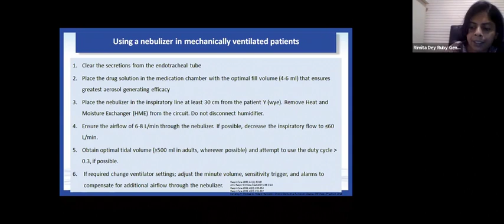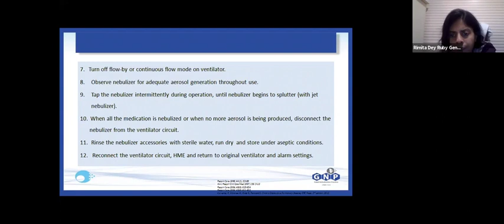You can turn off the continuous flow or flow mode on the ventilator if it actually creates a problem. Observe the nebulizer for adequate aerosol generation throughout its use, right? So you need to see the mist. If there is no mist, probably your nebulization is not working properly. You can tap the nebulizer intermittently during operation until the nebulizer begins to splutter with a jet nebulizer. When all medication is nebulized and when there is no aerosol being produced, disconnect the nebulizer from the ventilator circuit. Rinse the nebulizer accessories with sterile water, run dry and store under aseptic conditions. I don't know how frequently it is done in our ICUs. Reconnect the ventilator circuit, HME, and return to the original ventilator and alarm settings. This is how an ideal process has to be done all the time, right?